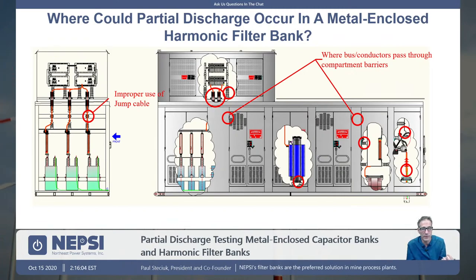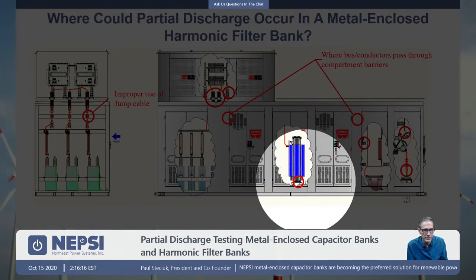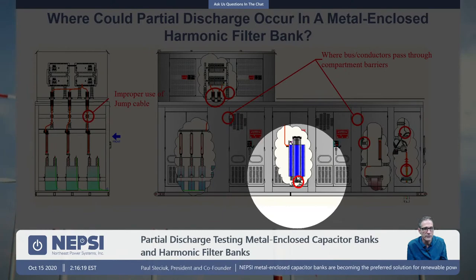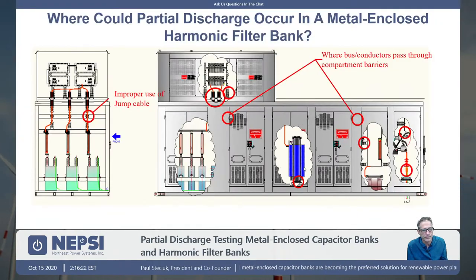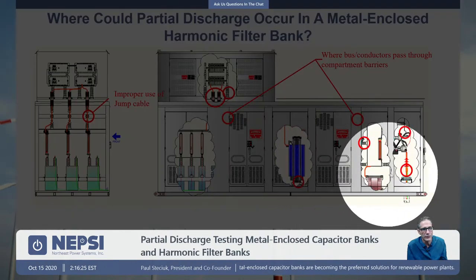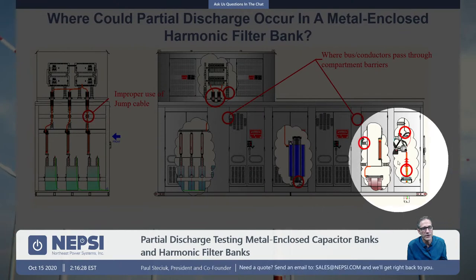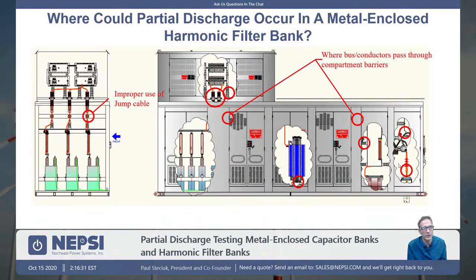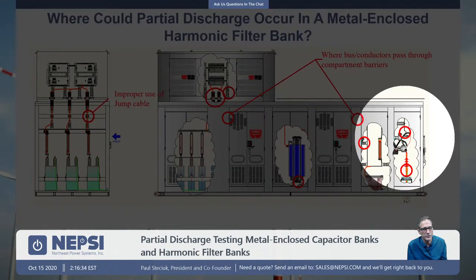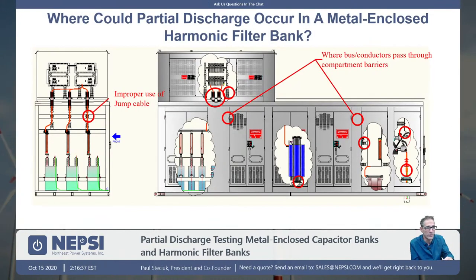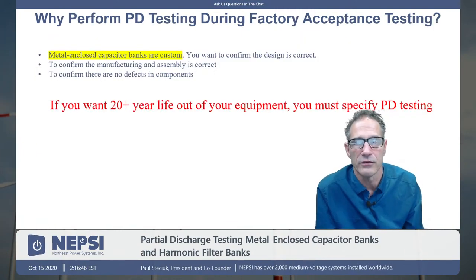It's very common that people are passing medium voltage jumper cable through those locations, and if it's not done properly, you'll have partial discharge there also. Down here at the reactors, we want to make sure that the reactor itself is properly grounded. Where else? At the terminations. Really this doesn't impact us, but terminations are a very common place where you get partial discharge once it's installed in the equipment. And then the last one, which is where the bus bars come into the disconnect switch. We have a terminating bus bar joint there, and oftentimes we might get partial discharge off the end of that bus bar. So just some locations to think about and look at.